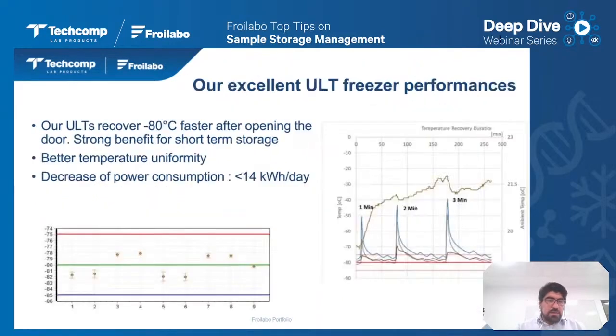Then we also did a lot of performance tests. We've done it a little differently from other people, because we realized that when people are using it, it's not just a matter of keeping the door of the freezer open for 10 or 15 seconds. They need at least 1 minute with the door open to move the samples around. By talking to our customers and from our market experience, we found that 1 minute, 2 minutes, and 3 minutes are the realistic times.